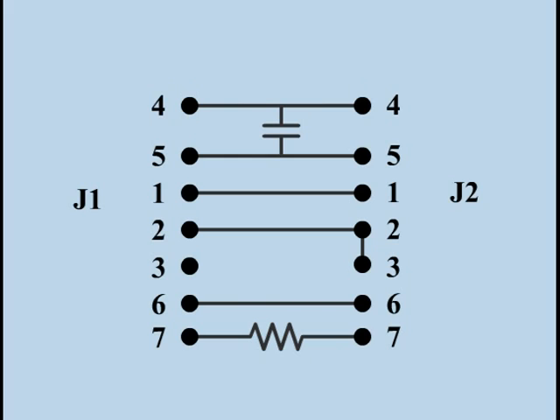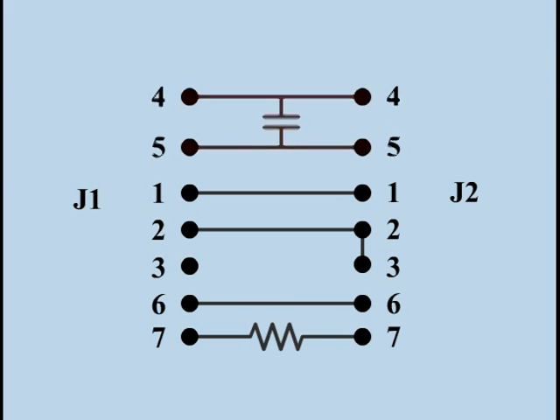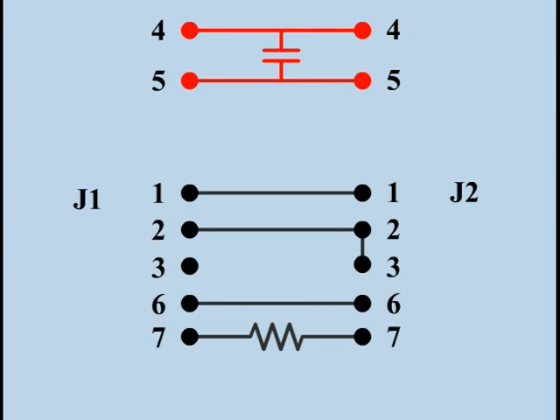Instead, Cirrus testers link the two nets together for the hypot test. This means that all points in linked nets are raised up to high voltage simultaneously, while all other nets are tied together at 0 volts.